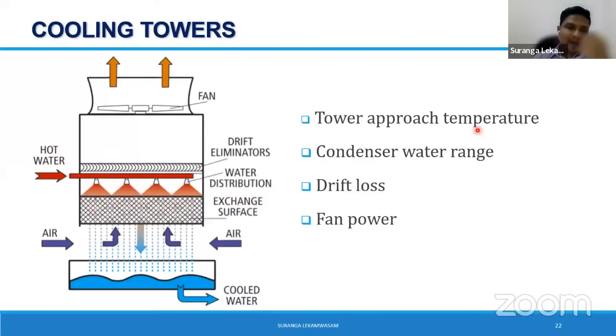Then cooling tower approach, that is again very important because this approach defines your cooling tower efficiency. What is the approach of the cooling tower? Approach means the cooling tower exit temperature minus your average ambient wet bulb temperature. Let's say you run your cooling tower at 37 and 32, and your ambient is 27. So 32 minus 27 is your approach. That is 5 degrees, right? So again, you have to specify that to select the cooling tower.